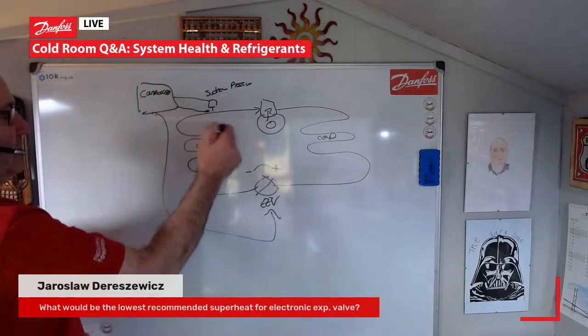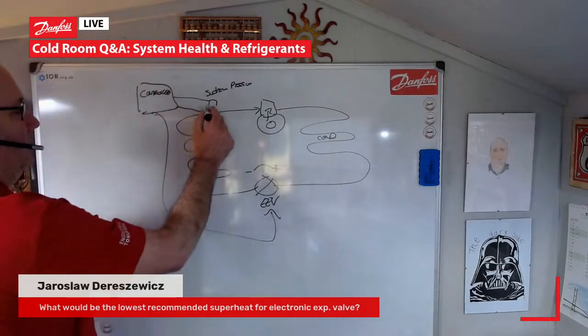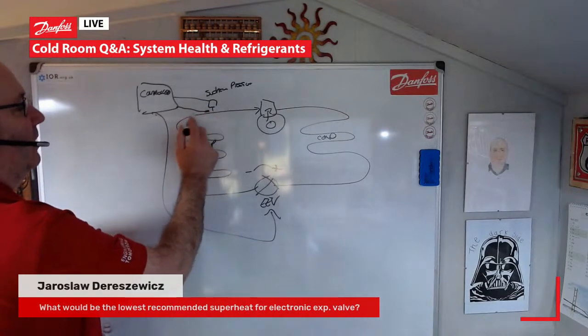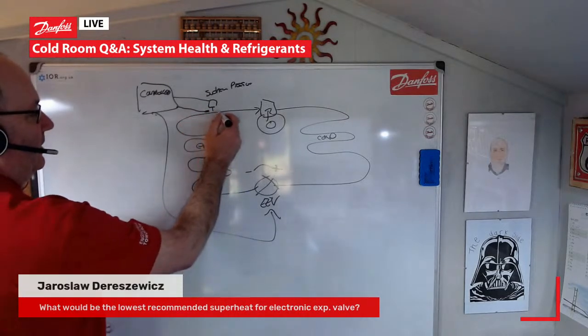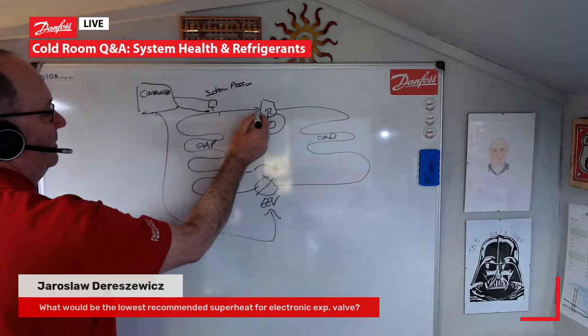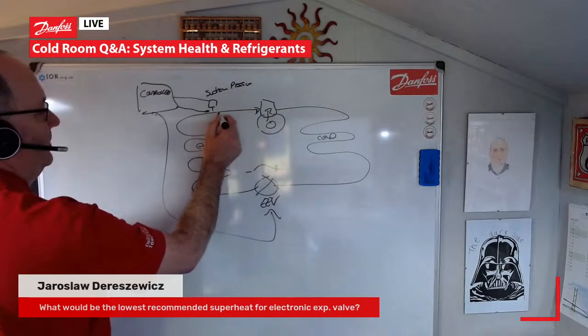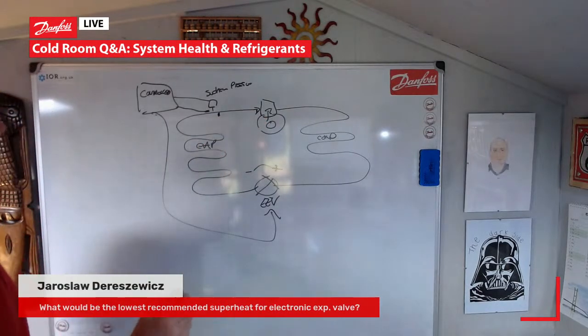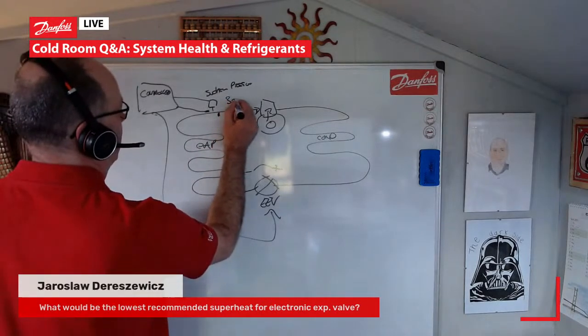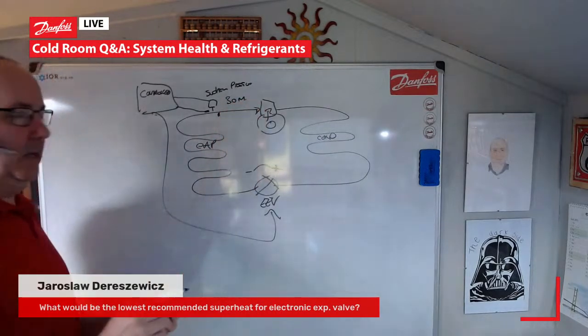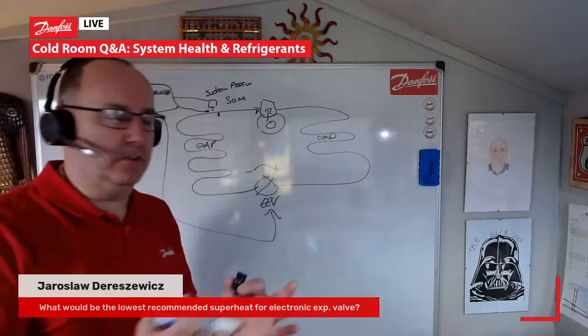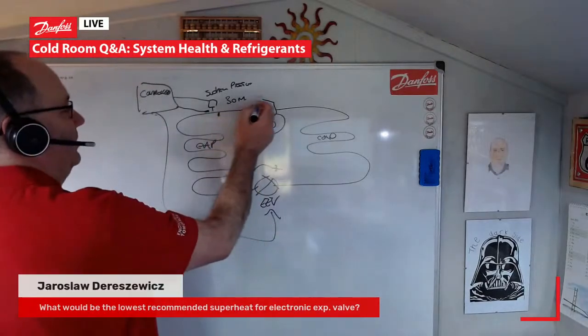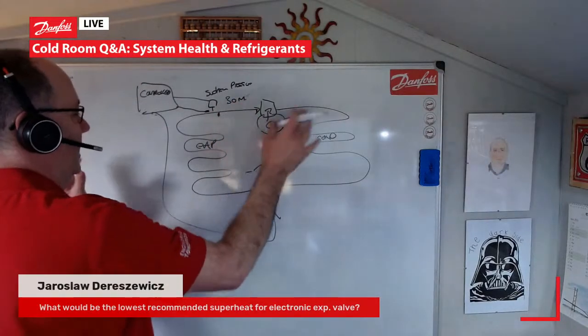So 6K, it would be absolutely fine. I wouldn't go any lower than that. The thing that I always think practically, that distance. Now, if we've got 30 meters of pipe, I'd be a little bit more flexible, because you've got 30 meters of pipe, picking up a bit of superheat in that line, absolutely fine.